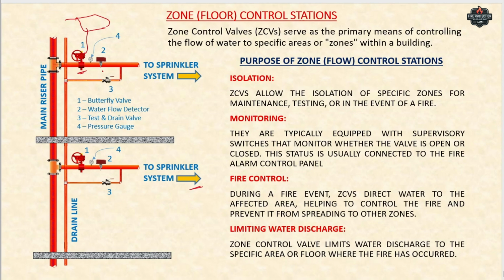Now the next is here. You can see one more thing, the flow control testing. That means here you can test the system. This is the test and drain valve. So you can open the valve and test the system. No need to run the sprinkler, no need to have an actual fire and then test the sprinkler. Without an actual fire, you can just open this valve. When you open this valve, the water will start to flow up this side, and then this flow switch will detect the flow of water. This is also connected to the fire alarm.